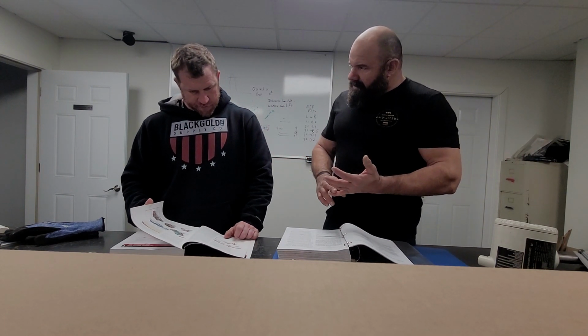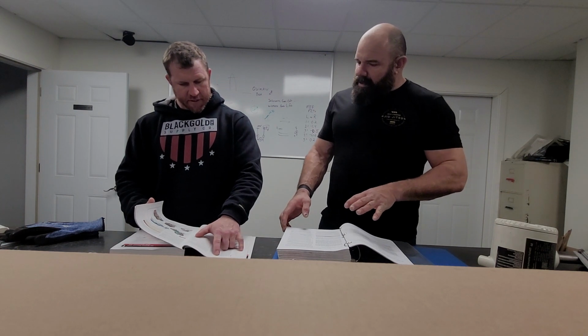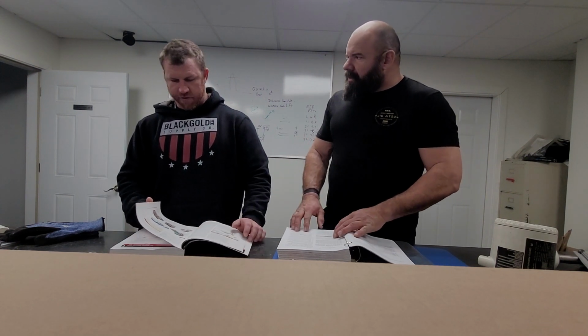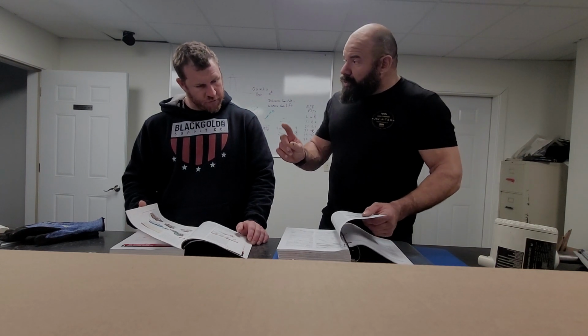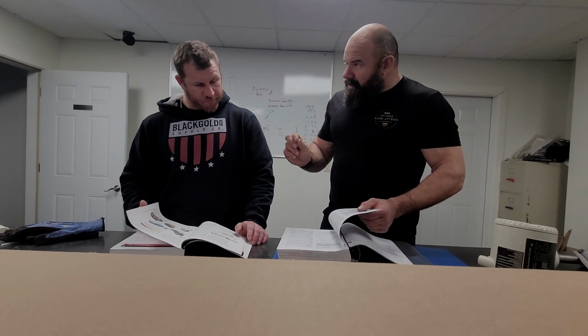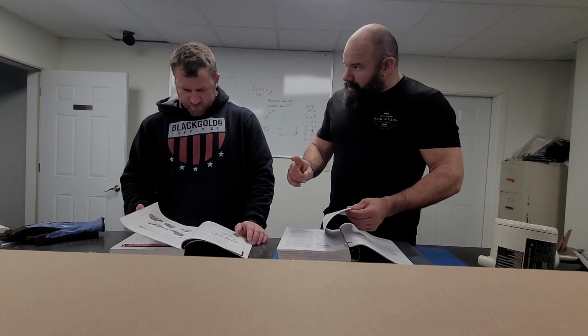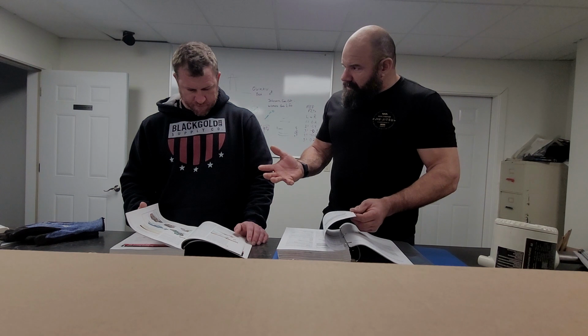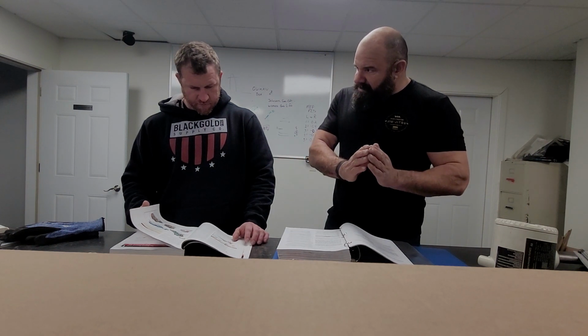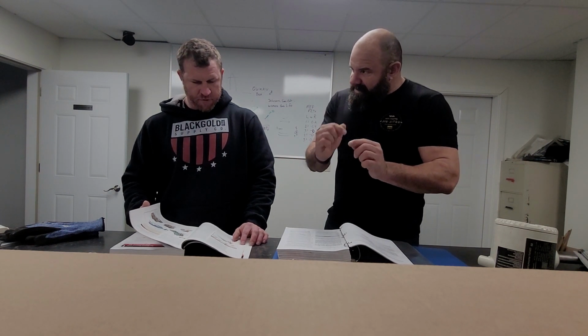Readily accessible and within sight are terms that are used in the NEC all the time. What you want to know is what article it's referenced to. Article 100 is all the definitions that are used in more than one section. If it's just used in one section, like child care facilities, which are only used in special occupancies, it defines it in that section.